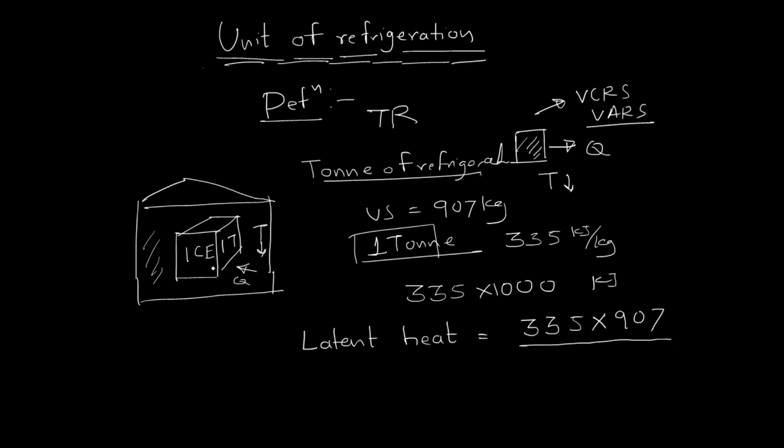This particular melting process should happen within 24 hours. Then we will divide it by 24 hours, convert it into minutes and then into seconds. If we solve this, we will get an answer equal to 3.51 kW. This is the unit of one ton of refrigeration.